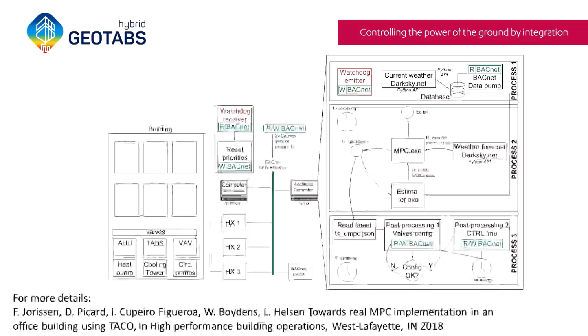We have a script for checking whether our MPC is running, and if not, it falls back on the existing rule-based controller, stopping writing on this BACnet layer. We also have a script that periodically repeats itself, for instance once every hour, that computes set points for the various components in the system.